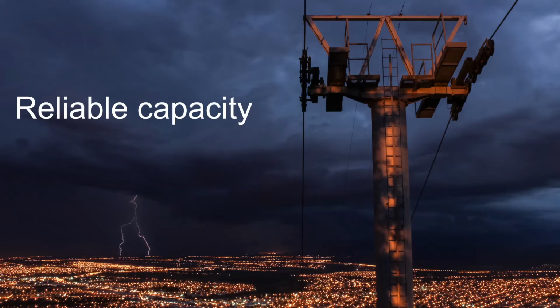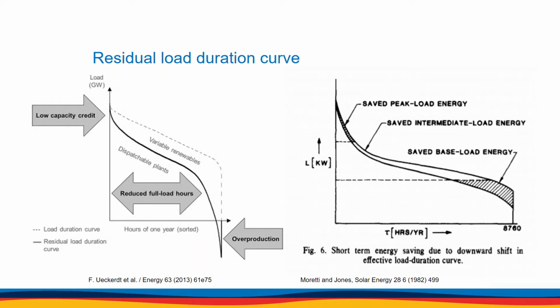we look at this? Well, we can look at the load duration curve, which shows the relationship between generating capacity requirements and capacity utilization. Our top curve shows the load duration curve, and the lower curve shows the residual load duration curve, where variable output is treated as a negative load. We can see that to the left of the curve is where peak load generation saved by variables is shown. Typically, we see that very little peak load generation is saved, showing that VRE can't help to meet peak demand and therefore doesn't reduce the amount of installed dispatchable generation required.